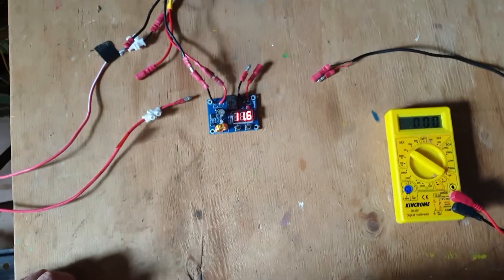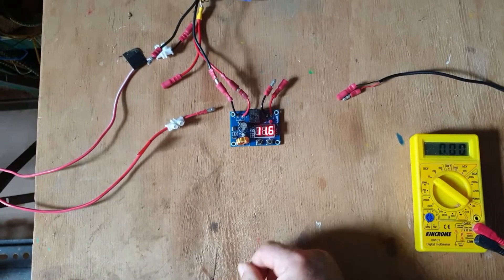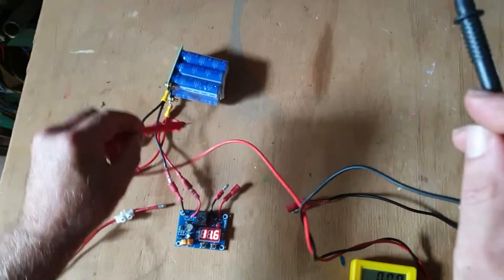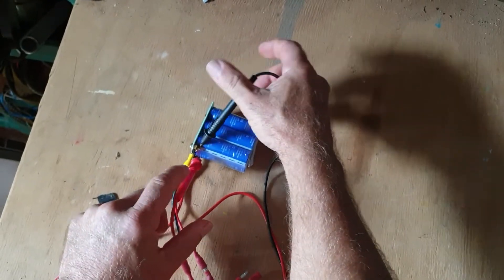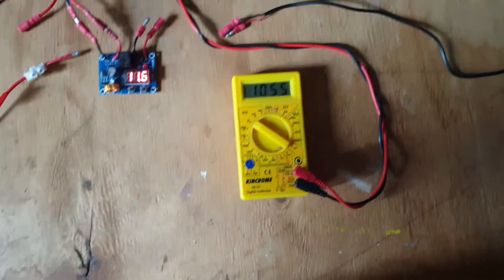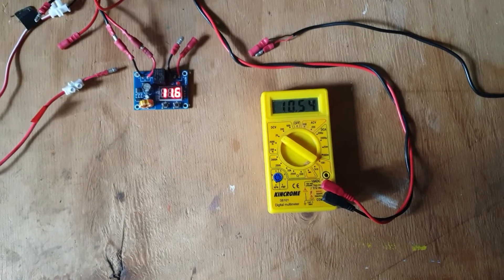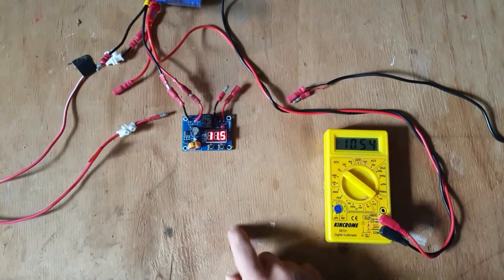The first thing I need to do is check that the voltage is correct on this module. I'm just going to hook up my own voltmeter. It's about one volt out — it's actually too high. My voltmeter says 10.5, but the unit says 11.5.